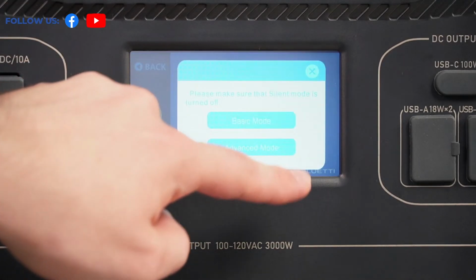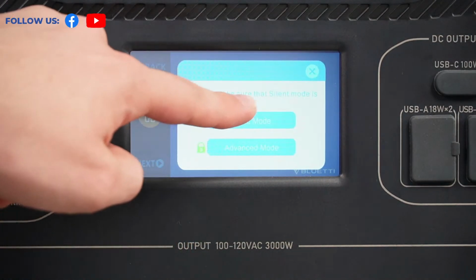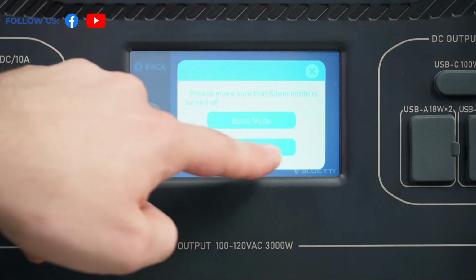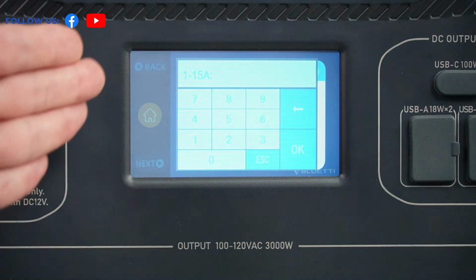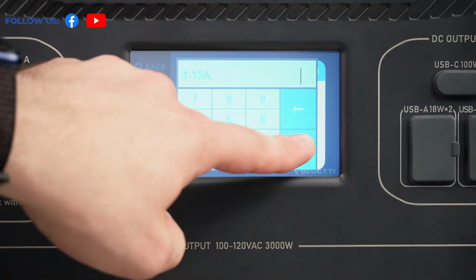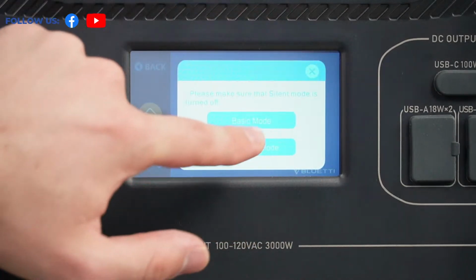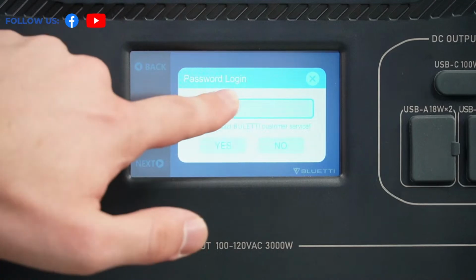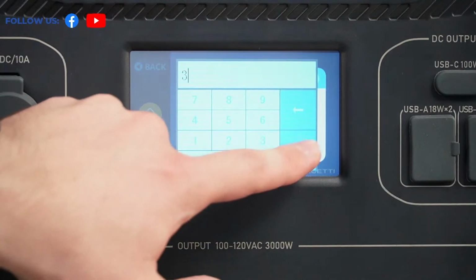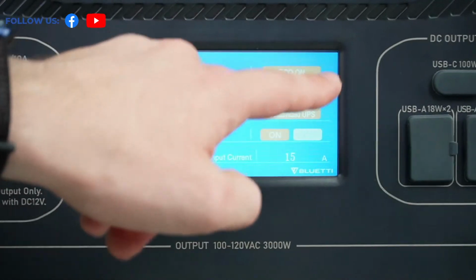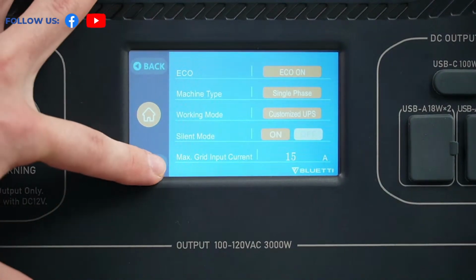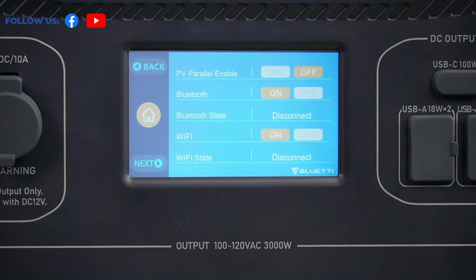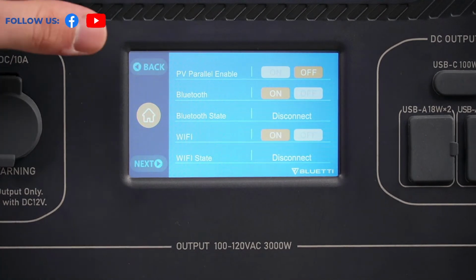Max grid input current, you can set it even more than 15 amps. Here's the basic mode, which can be set by you from 1 to 15 amps, but if you want to go higher you need advanced mode. You need a password, I'm sorry, this is how things are done right now at BLUETTI. I don't know the password, you have to email customer service. I saw some complaints, but sorry guys, this is how we do it right now.